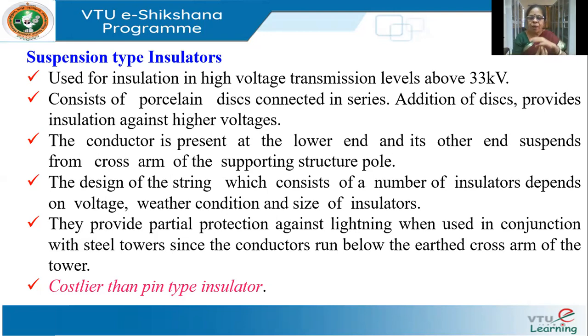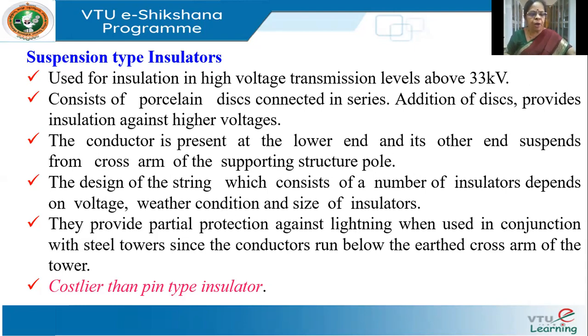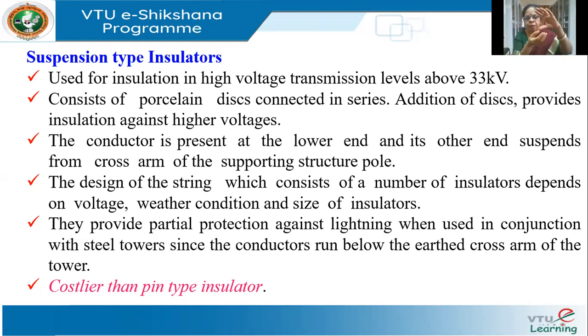At the bottom end, it supports the conductor, and on the top end, it is connected to the cross arms of the supporting structure. These discs have to be designed, and we will see how in the next slides. These type of insulators also provide partial protection against lightning when used in conjunction with steel towers, since the conductors run below the cross arm. If a lightning strikes, it will strike the cross arm, which would have been grounded, so the conductor is protected.